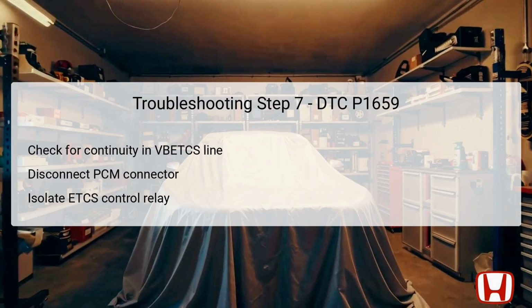If no continuity is detected, it suggests that there is an open in the VB ETCS RLY OUT wire within the circuit. This issue should be addressed by repairing the open wire located between the PCM and the ETCS control relay, allowing for proper electrical pathways to enable functionality.